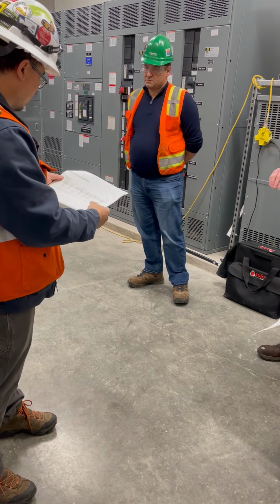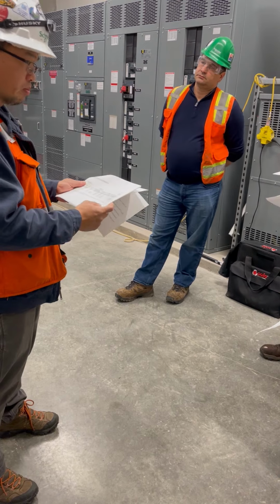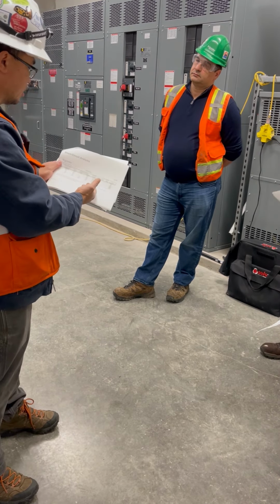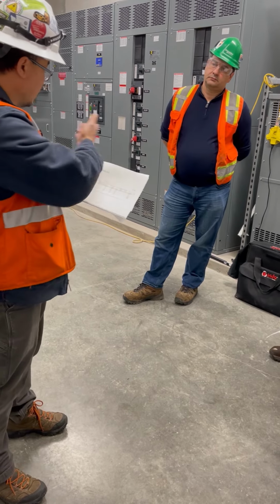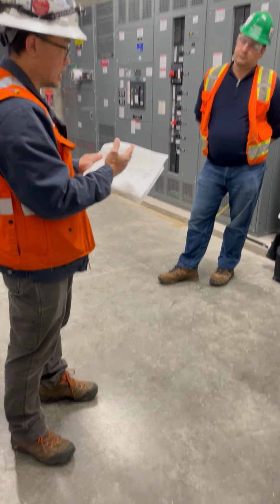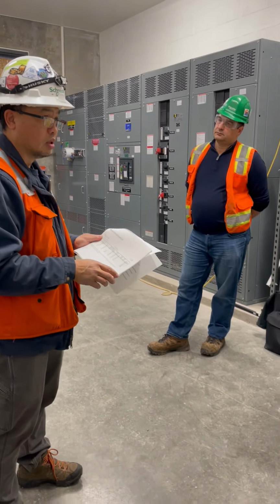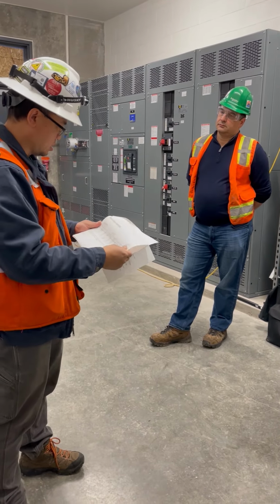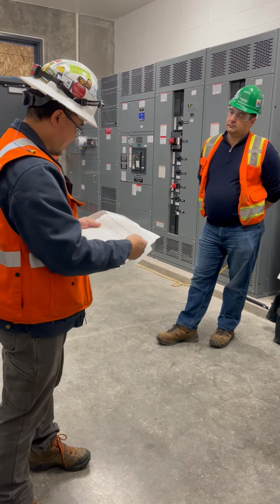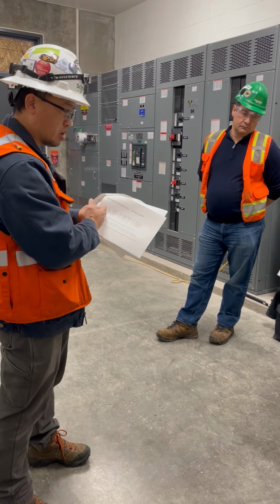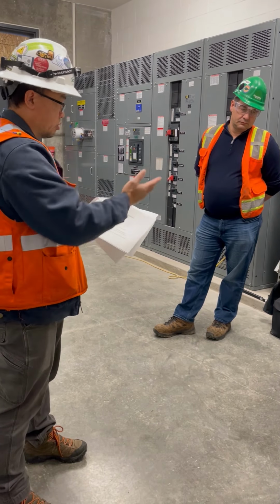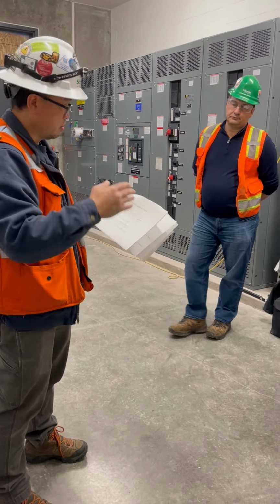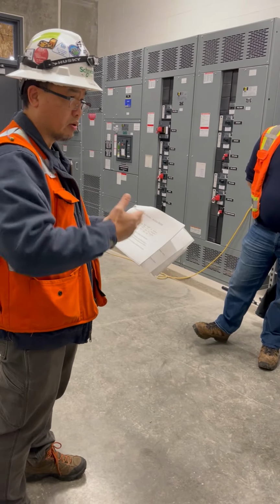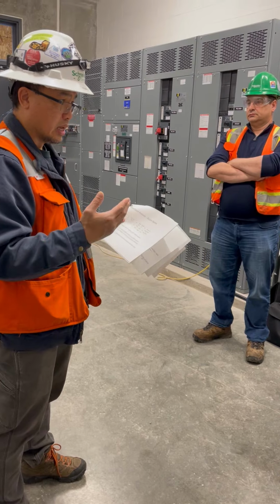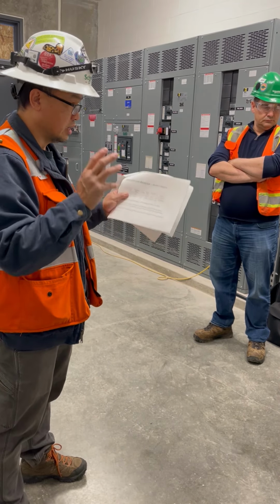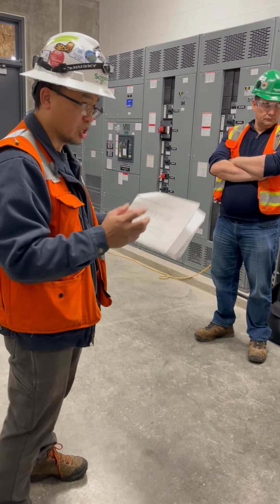So once we do that, I don't know if you guys have seen the report, but in the report you'll see the short circuit current value, which we calculate based on the available fault current and the equipment in each panel. It's a lot of data to analyze. Then we analyze whether that available fault current is greater or less than the equipment rating. You want equipment rated a little bit higher than the available fault current. Otherwise, if there's a fault, it can't contain the available fault current, so there's the possibility it could explode.